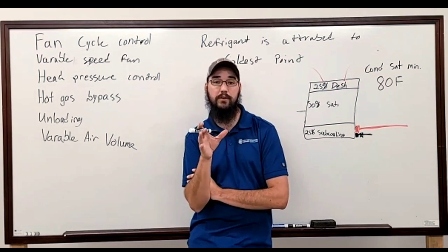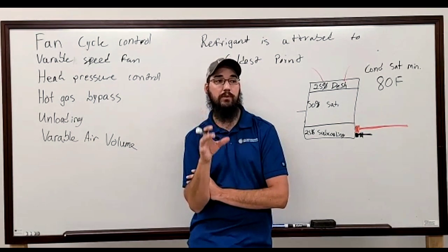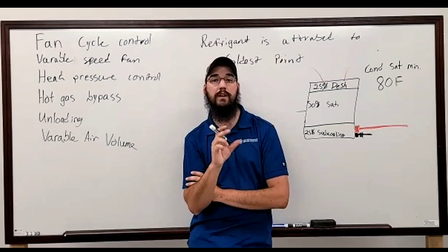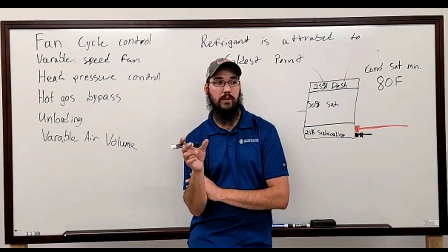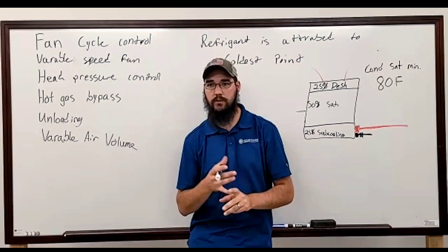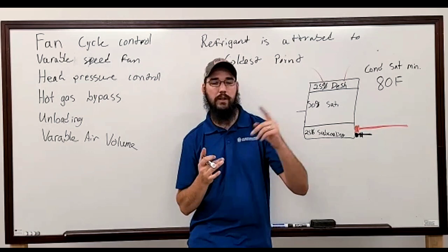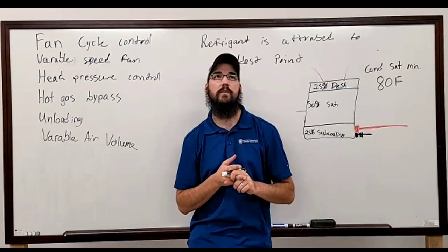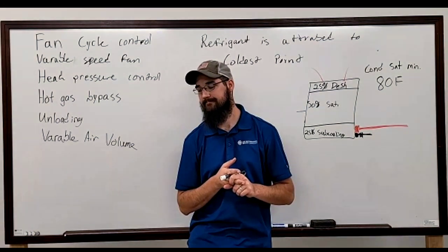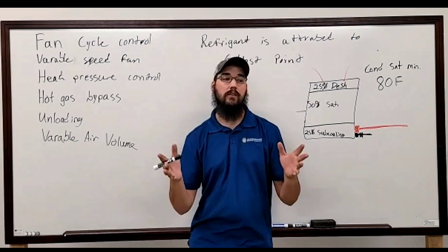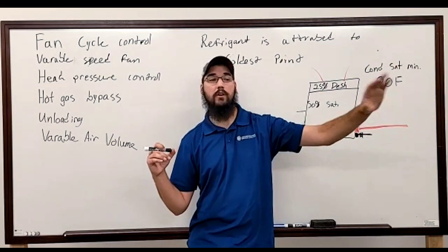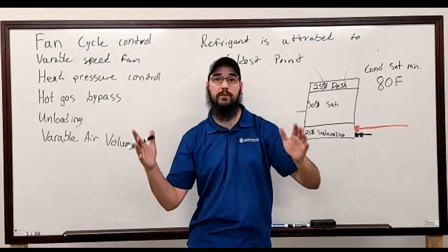The main focus is not actually head pressure control. Even on those systems that have variable speed compressors, the fans are still responsible for controlling the head pressure. The compressor is responding to the load and demand on the equipment. It's the same control logic either way, whether you're looking at an air-cooled chiller, Yorks specifically, or an outdoor air unit. The compressors are basing off of whatever, whether it be return air, entering water, or leaving water load. They're set to achieve a certain goal.